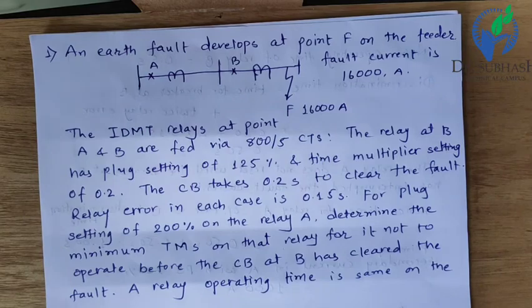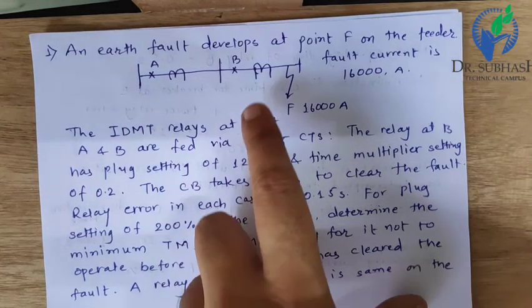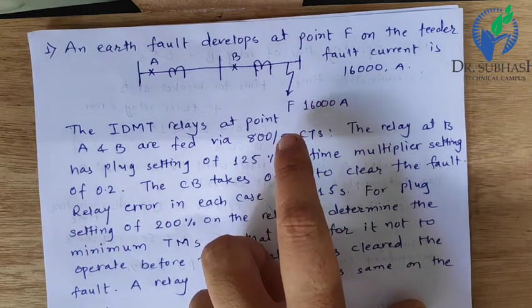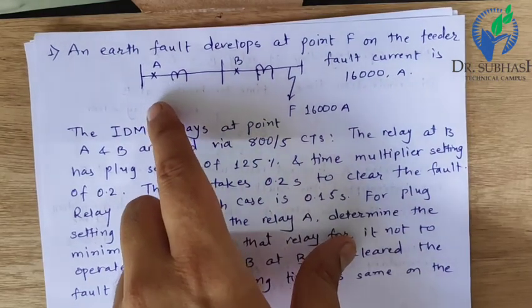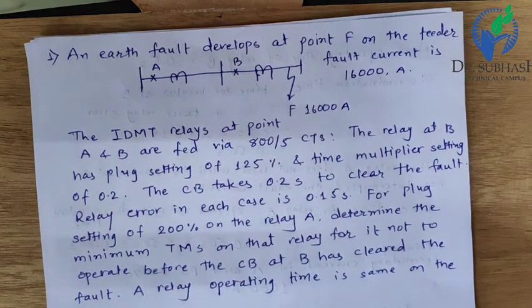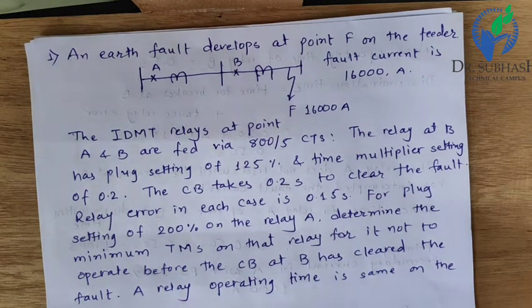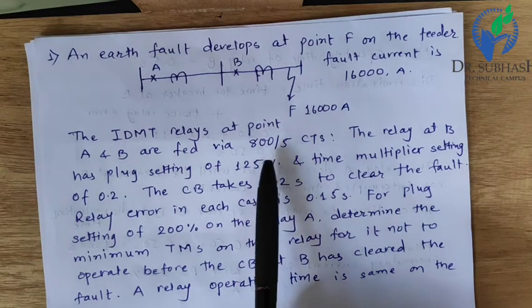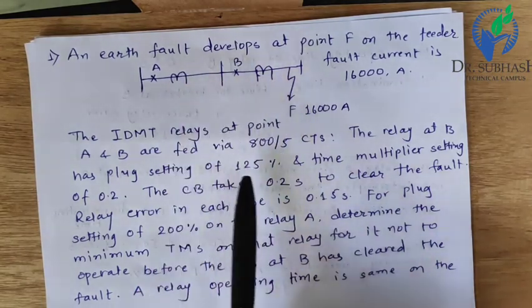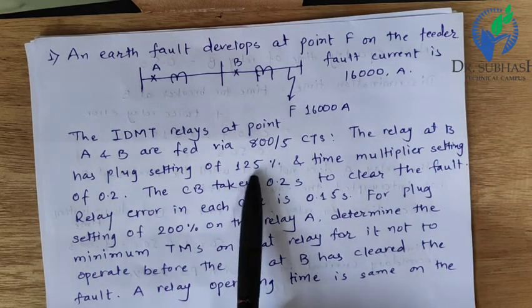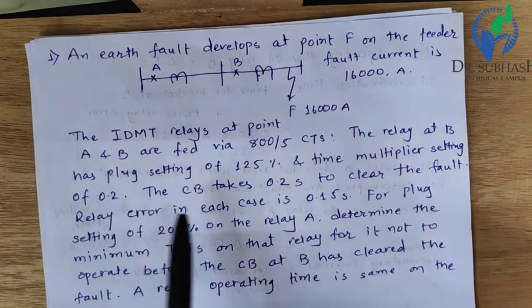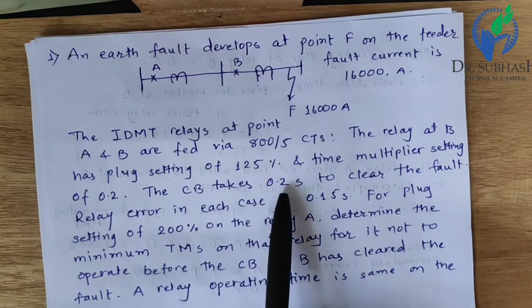First Numerical: an earth fault develops at point F on the feeder. The fault current is 16,000 Ampere. Bus bar A and bus bar B with two breakers and two CTs. The IDMT relay at point A and B is fed via 800/5 CTs. The relay at B has Plug Setting 125% and Time Multiplier Setting of 0.2. The CB takes 0.2 seconds to clear the fault.